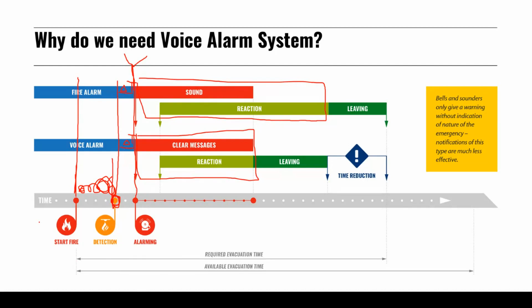If there is no reaction to clear the detection, the alarm goes off automatically, and this is where it all starts—the point where we begin to hear messages spread throughout the building from speakers or sounders. The reaction time with sounders in the fire detection system is much, much longer than with a voice alarm system. That's why we use voice alarm systems compared to simple sounders—it simply takes less time for people to react, leave the building, and escape the danger.